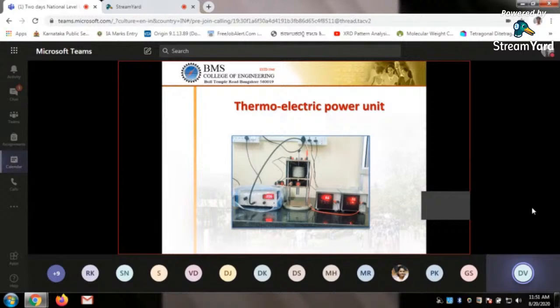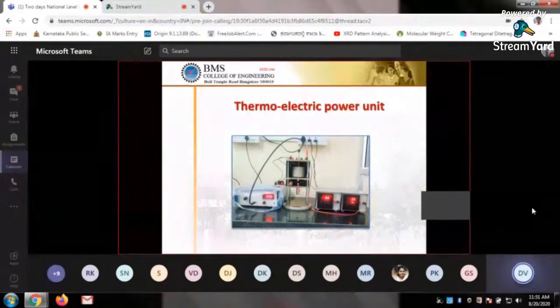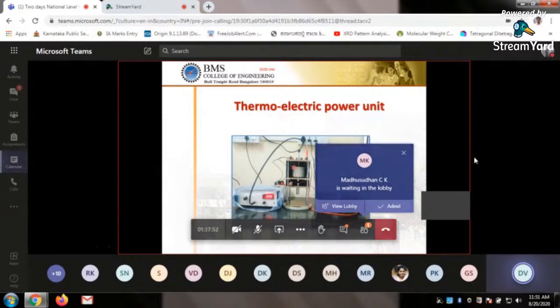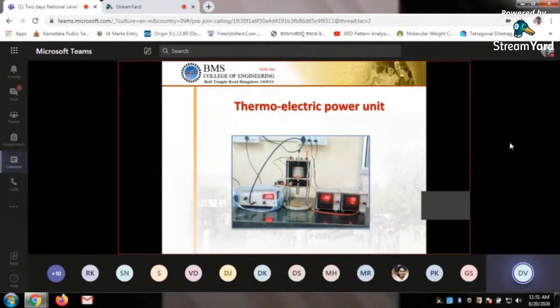We have a simple instrument in our lab. So how does it work? This is the higher temperature side. We have a furnace here, connected to a thermocouple, and we can read the temperature. The lower one is at room temperature, so there is a temperature difference. This is where we keep the sample. The upper surface of the sample is at higher temperature, and the lower surface is at lower temperature. You can keep a water glass here with cold water, so that the lower surface is at room temperature and the upper surface is at higher temperature. You can see the values also.